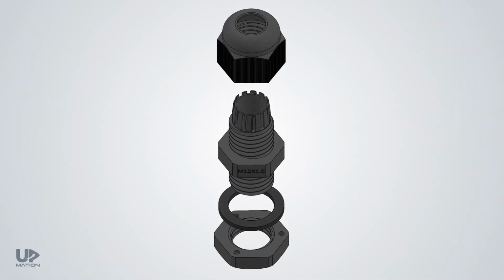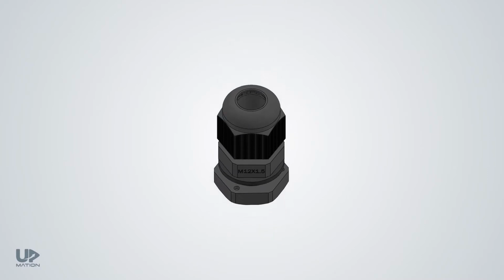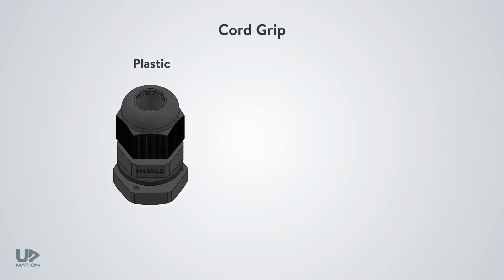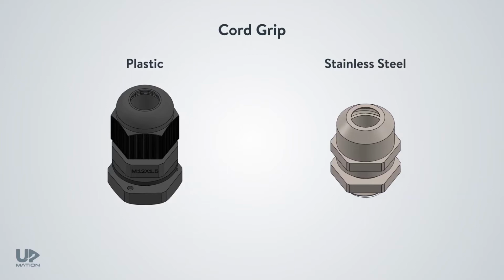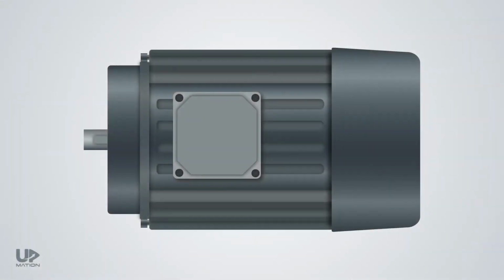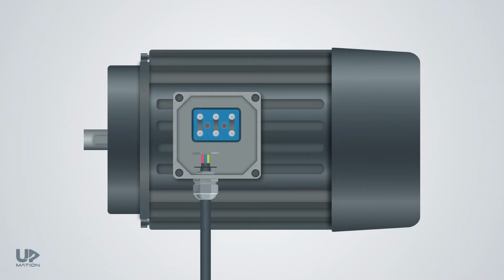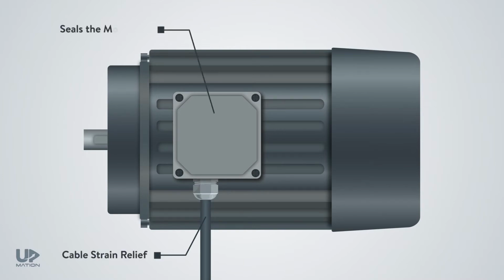But before passing the cables through the holes, there is another component that we should add, known as a cable gland. A cable gland, which is also called cord grip or cable fitting, is a piece of plastic, stainless steel, or even aluminum part with the standard sizes to provide proper cable connection to a device. For instance, if I need to attach this cable to an electric motor terminal box, I first need to dismantle the gland and install that on the cable. Then I will bring the cable inside the box. Finally, I fasten the cable gland to the terminal box using its hexagonal lock nut. In this way, the cable is protected against any kind of possible strain. Moreover, it seals the motor terminal box and prevents entry of water or any kind of liquid into that.